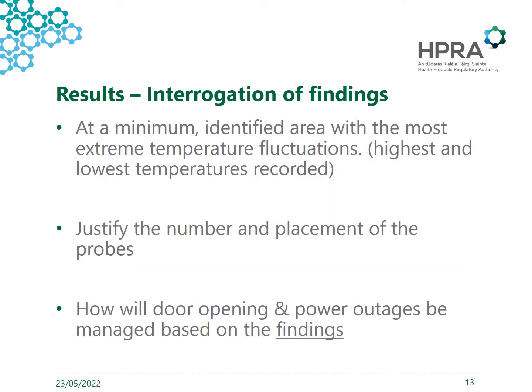After you've conducted your study and you have your data, it's important you interrogate the data and document the results. We know at a minimum the company should identify the areas with the most extreme temperature fluctuations, for example, the highest and lowest temperatures recorded, and place permanent temperature monitoring probes in these areas. But depending on space, it may also be appropriate to examine additional areas of flux and place probes in those locations. This is an area that's often overlooked. Companies go straight from the study to the conclusion without outlining any rationale or reference to the data to outline their justification. So justify the number of probes and placement of the permanent temperature monitoring probes with reference to the data. It's also important to document how the door opening and power outages will be managed, again with reference to the findings.